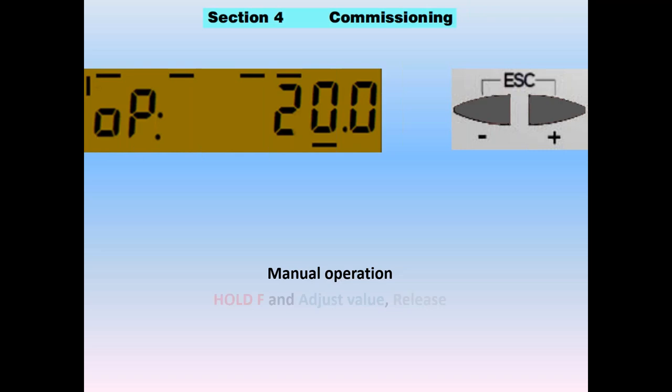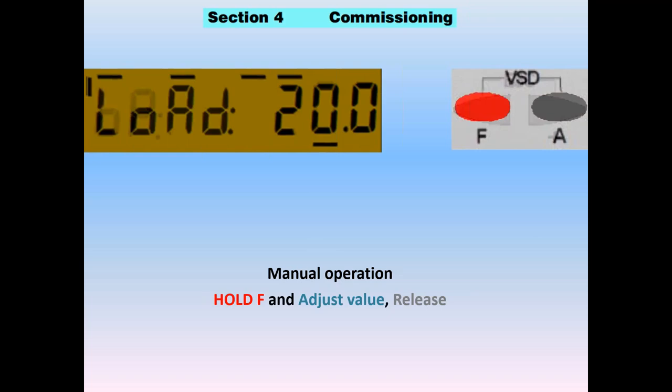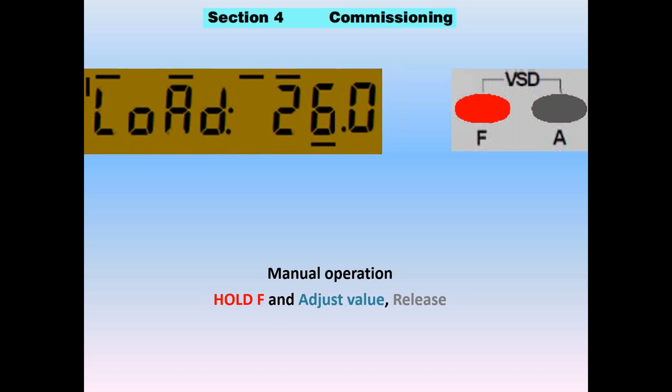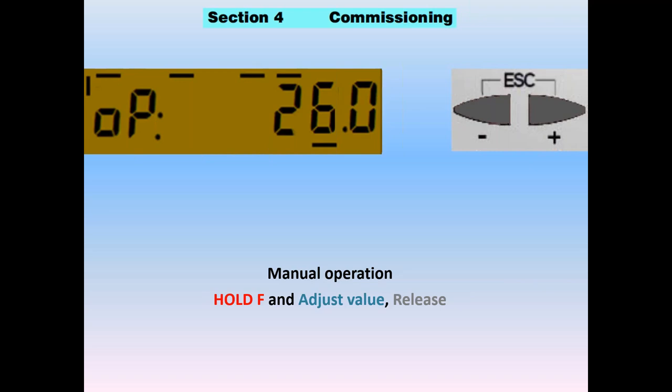For manual operation, hold the F key and while holding it, adjust the load number using plus or minus to set a value between 20 and 100. In this case, we'll go to 26% fire rate and release. The unit goes back and operates, staying at 26% fire rate. The display shows 26.0 flashing while running in manual, indicating the burner is in manual operation. A flashing operation percent means you're manually firing at that percentage.